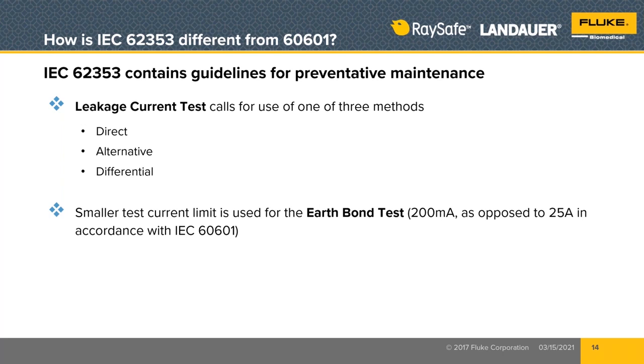Another thing to remember about IEC 62353 is that the test current used for doing the protective earth or ground resistance test is only required to be 200 milliamperes, whereas in the IEC 60601-1, we require 25 amperes of current flow. Now, this doesn't mean you must only use 200 milliamps. You're allowed to use 200 milliamps or 25 amps, but whatever you choose, stick with it.